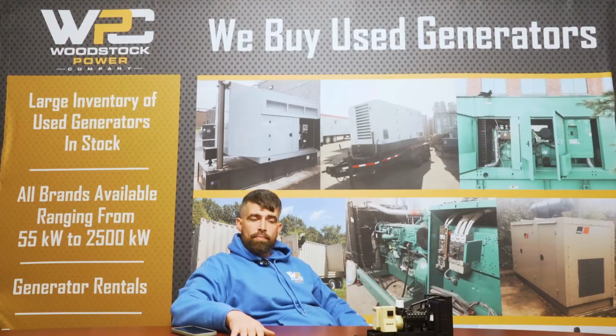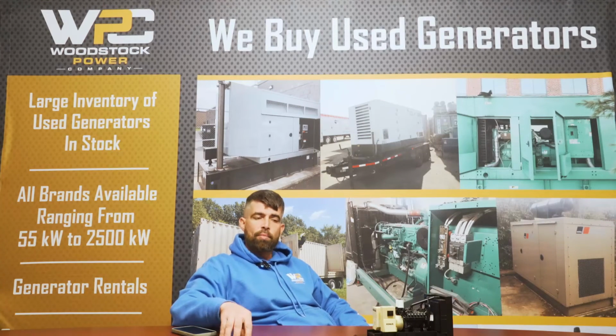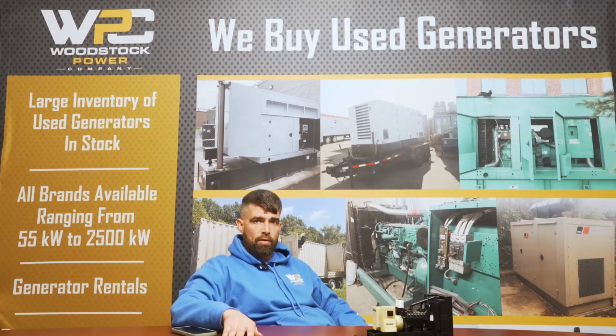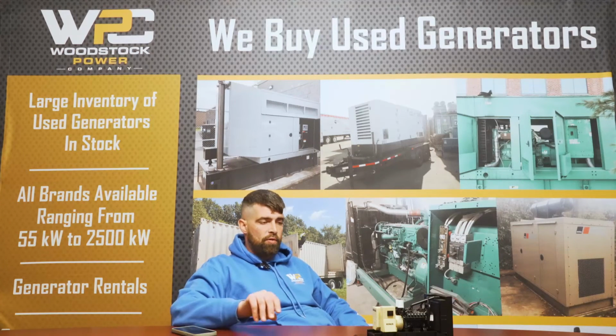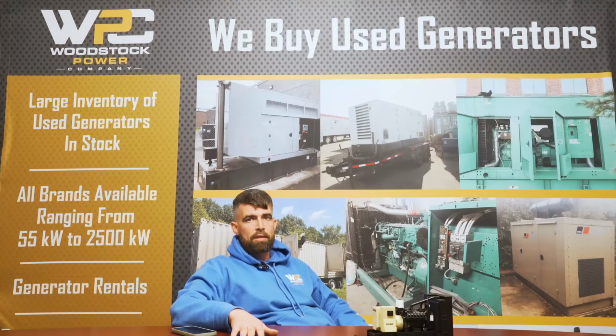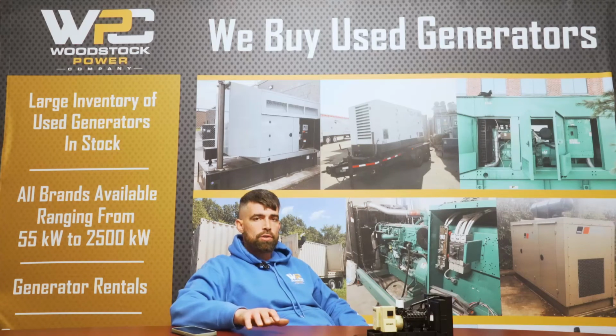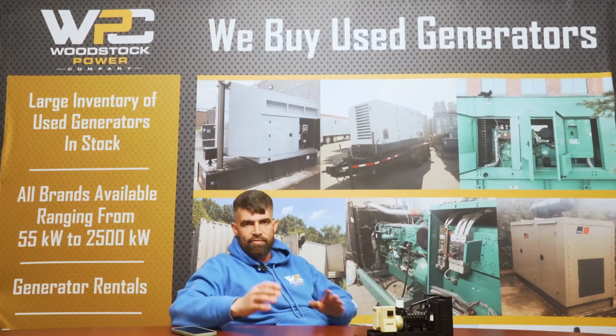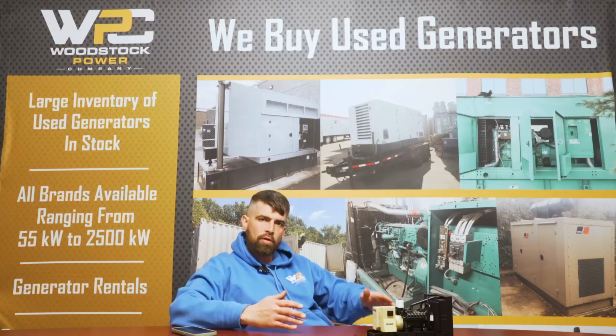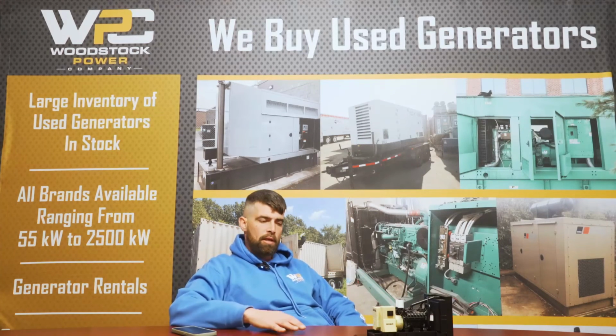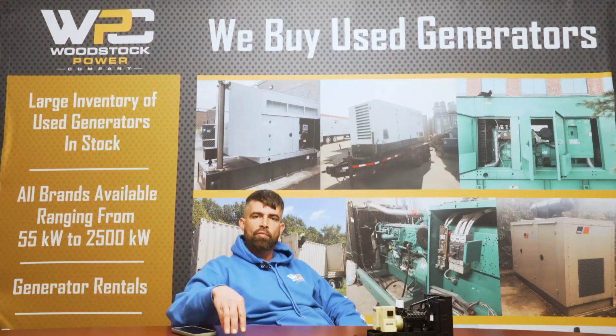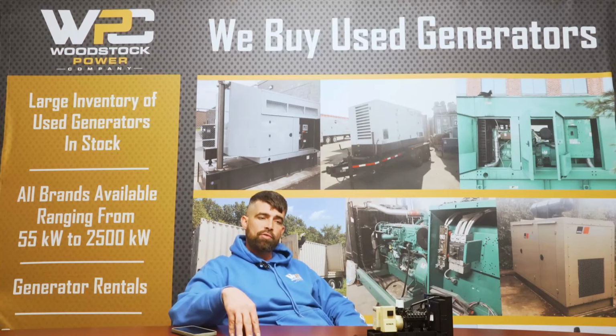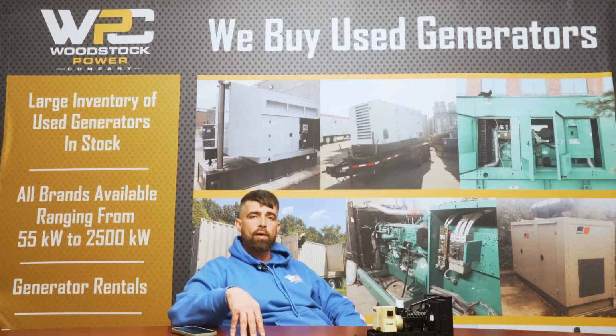So in summary, maintaining your generator is very, very important for the operation of the generator whenever you really need power. If you're not sure, if you don't have the time to inspect it and maintain it, make sure you sign a service contract with a service company, and they're going to come out to your facility and service your generator every, again, 250 hours or so. They have set times throughout the year where they do the load bank, the service and everything, and let them handle it. It's worth whatever the amount of money is that they charge for you to actually have your generator operating and giving you the backup power when you really need it.